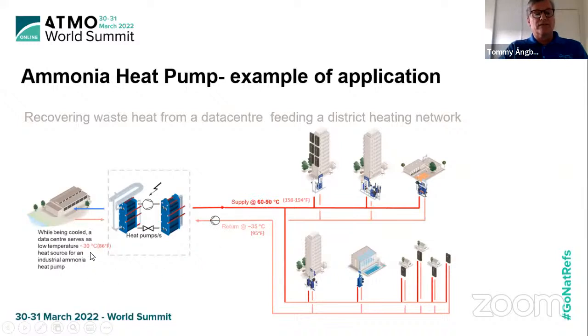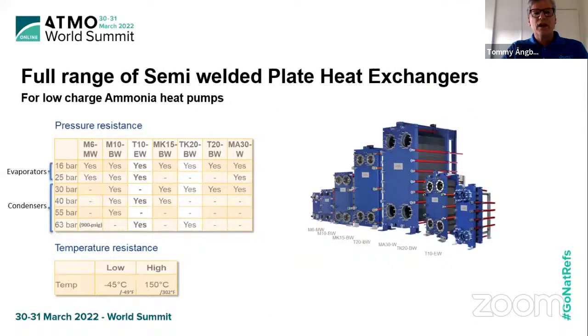Something like 30 degrees C, 86 degrees Fahrenheit, we can lift to 60 or 90 degrees, up to 90 degrees or more, around that temperature, 158 to 194 degrees Fahrenheit, useful, going into buildings for their space heating and tap water heating. A perfect example of an application for heat pumps and for ammonia heat pumps.